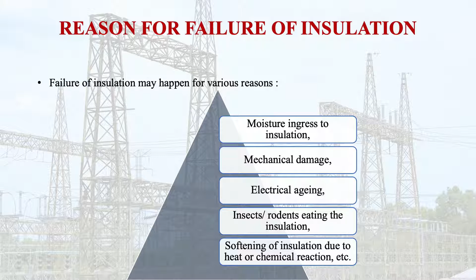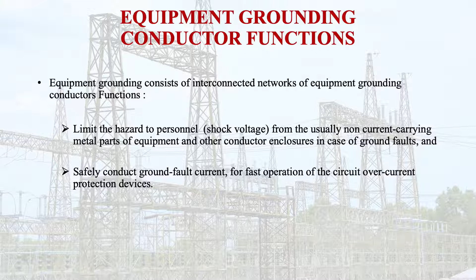Equipment grounding consists of interconnected networks of equipment and is used to perform various functions, like limiting the hazard to personnel, that is shock voltage, from the usually non-current carrying metal parts of equipment and other conductor enclosures in case of a ground fault, and safely conducting ground fault current for the fast operation of the circuit overcurrent protection devices. So for this purpose we need grounding.